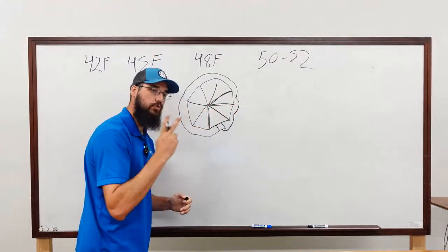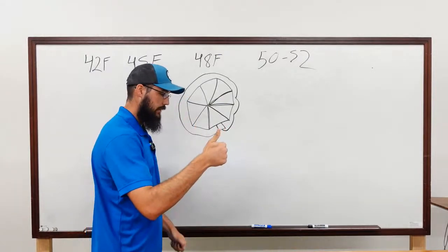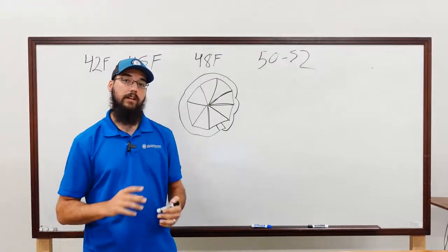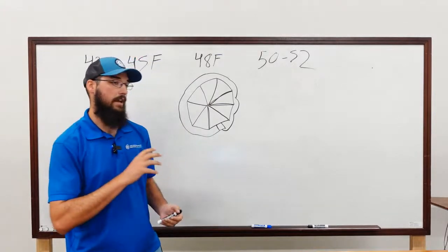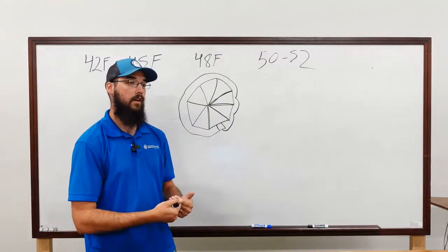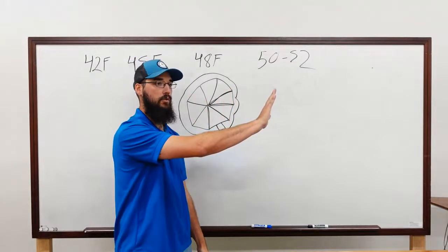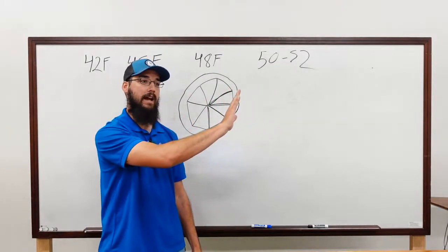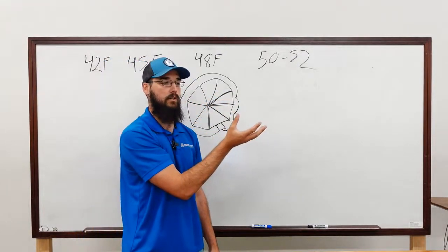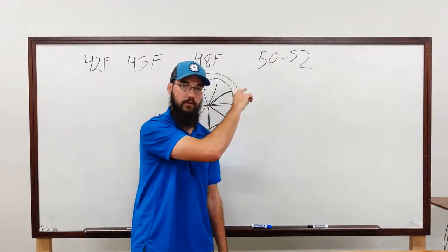This does two primary jobs. Job number one, and it's the whole reason why I call it a guide vane, is to create a pre-rotation on the refrigerant. Now, this helps improve efficiency. If we have refrigerant just moving in a straight line and then it slaps the nose of the impeller, that impeller has a lot more force that it has to apply to those refrigerant molecules in order to accelerate them and spin them out into the volute.